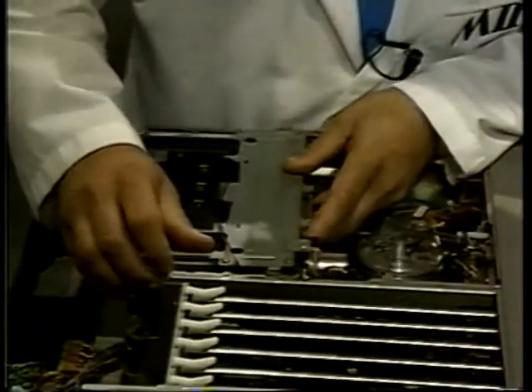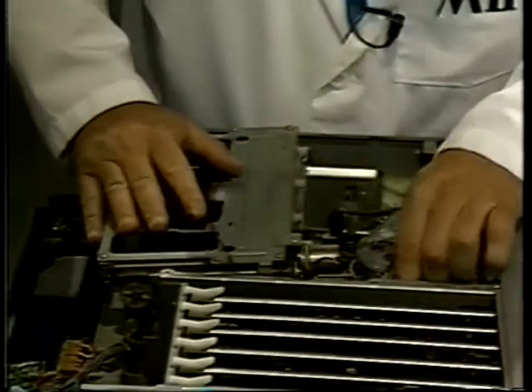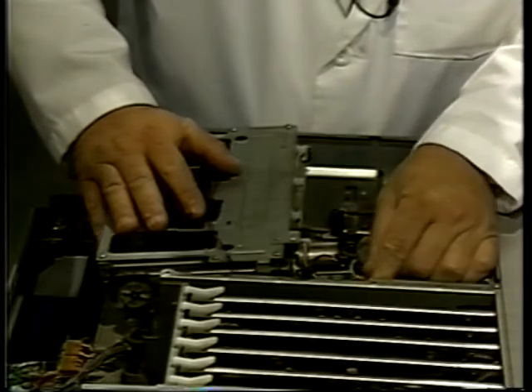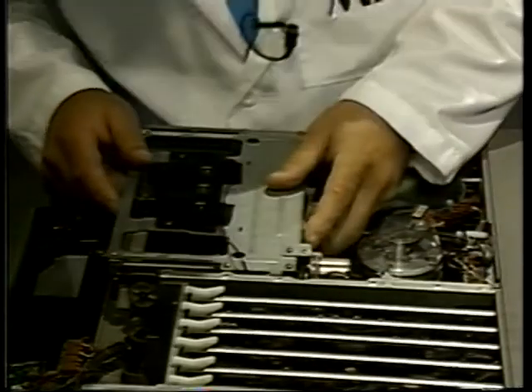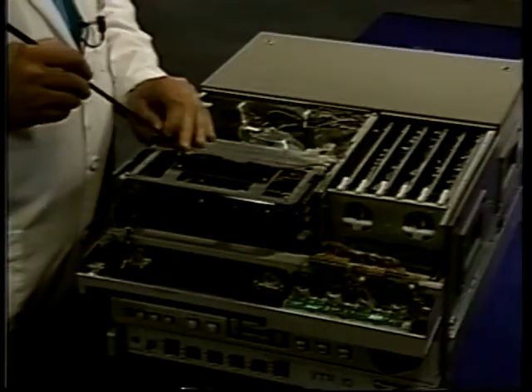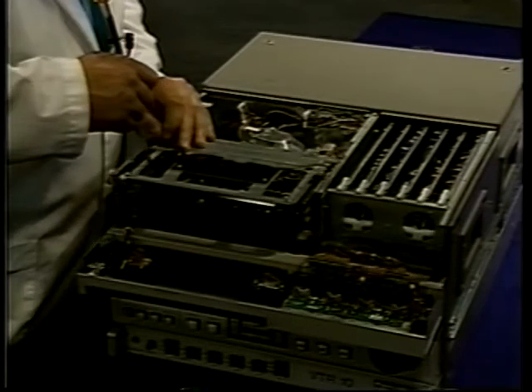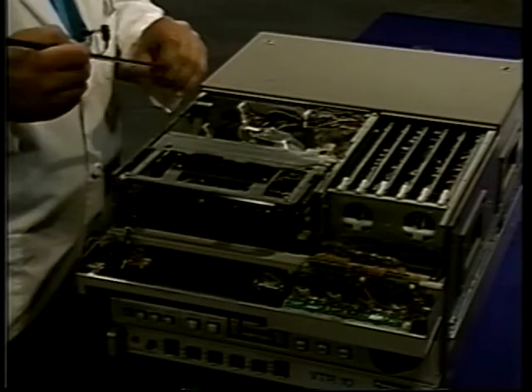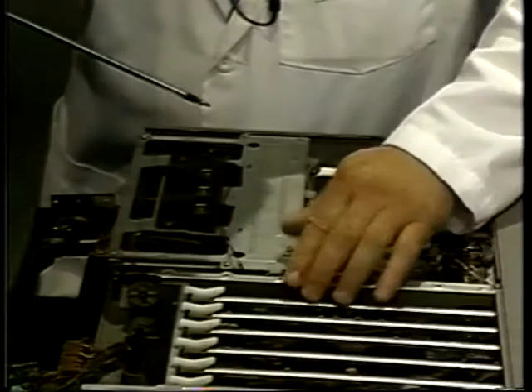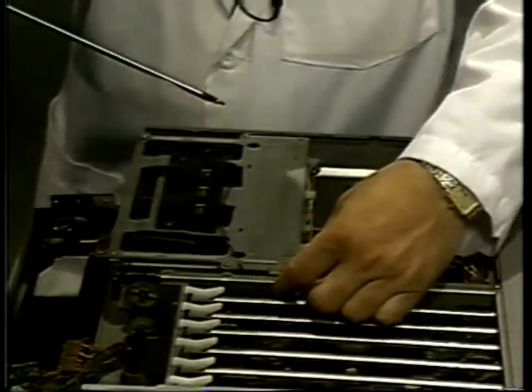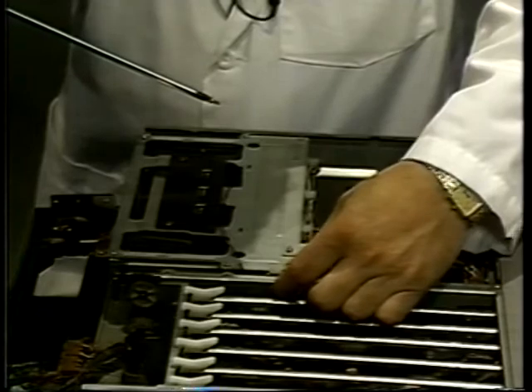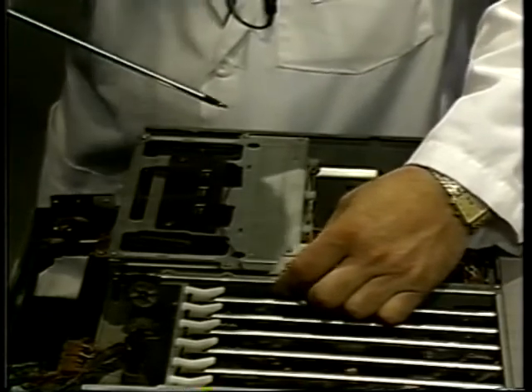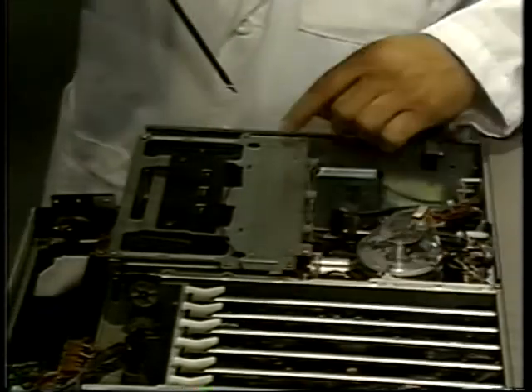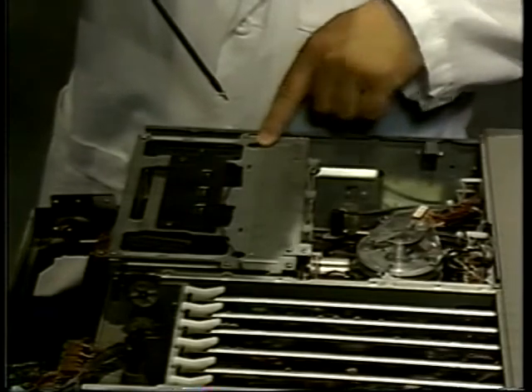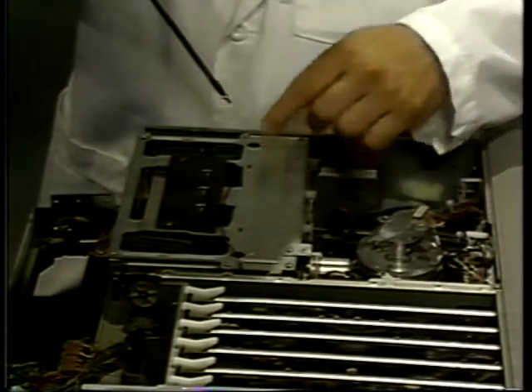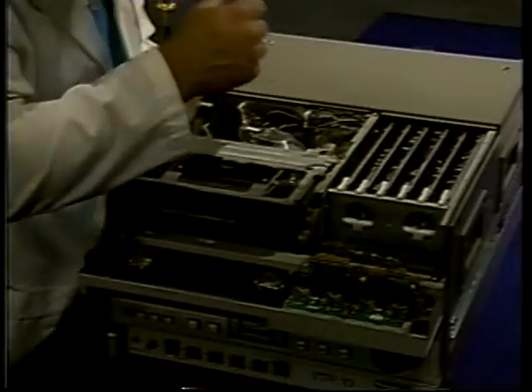The cassette assembly is loaded down, being careful not to pinch wires. Plug in the connector. Replace the 2 screws down in here and here. Move the cassette assembly out of the way to gain access to the other 2 screw holes by turning the loading motor. Replace the 2 screws in this hole and this hole. Tighten up all 4 screws.